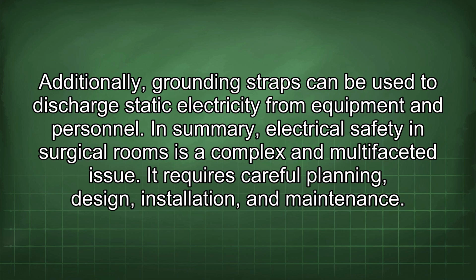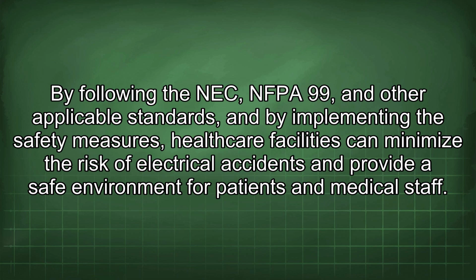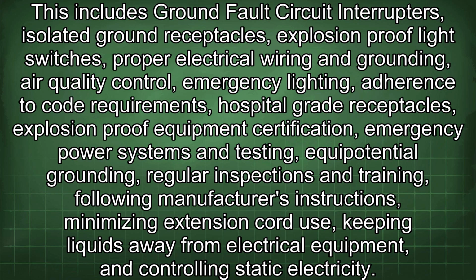In summary, electrical safety in surgical rooms is a complex and multifaceted issue. It requires careful planning, design, installation, and maintenance. By following the NEC, NFPA 99 and other applicable standards, and by implementing the safety measures, healthcare facilities can minimize the risk of electrical accidents and provide a safe environment for patients and medical staff. This includes ground-fault circuit interrupters, isolated ground receptacles, explosion-proof light switches, proper electrical wiring and grounding, air quality control, emergency lighting, adherence to code requirements, hospital-grade receptacles, explosion-proof equipment certification, emergency power systems and testing, equipotential grounding, regular inspections and training, following manufacturer's instructions, minimizing extension cord use, keeping liquids away from electrical equipment, and controlling static electricity.